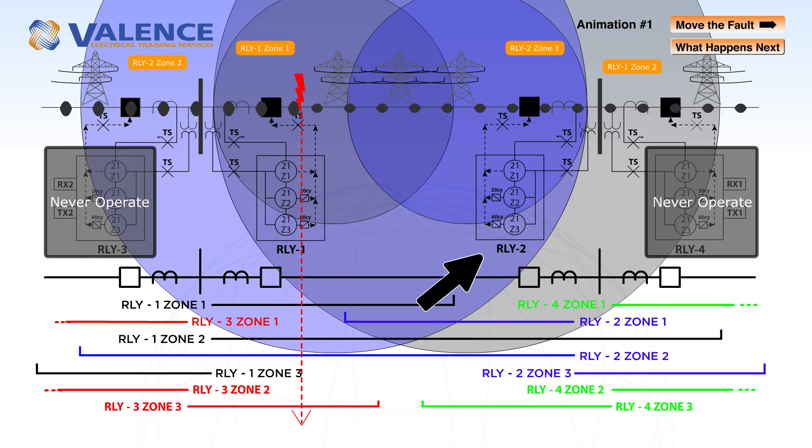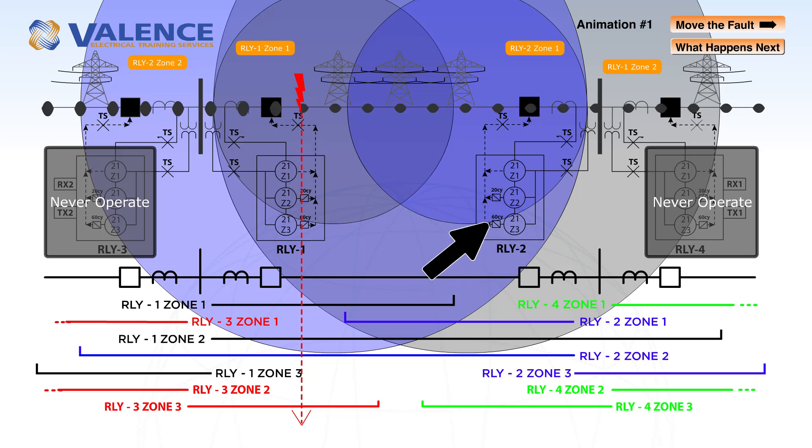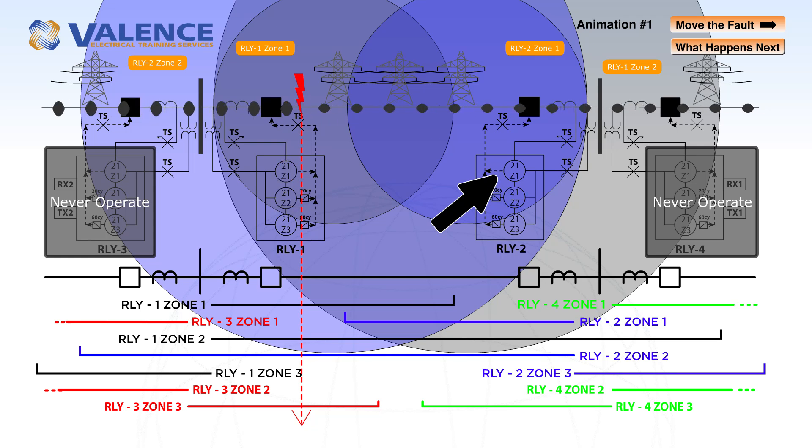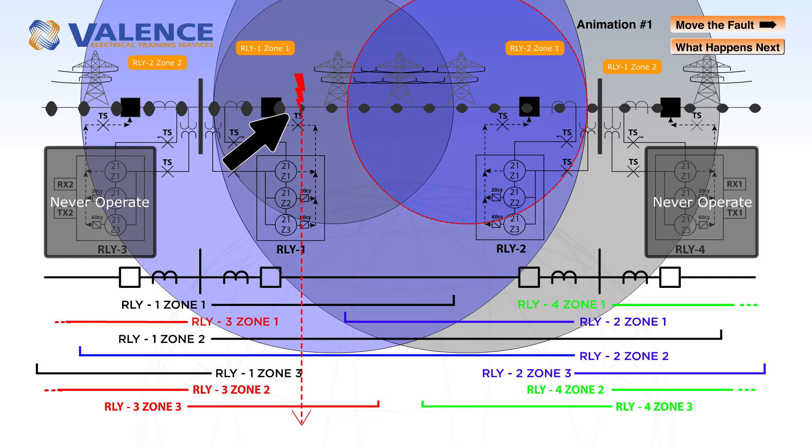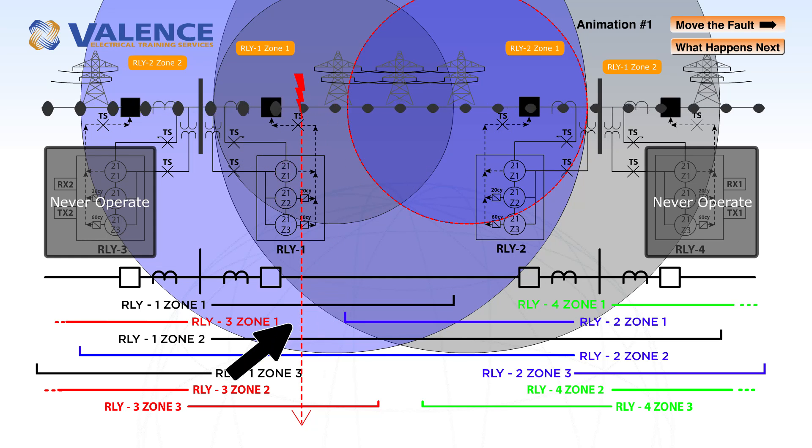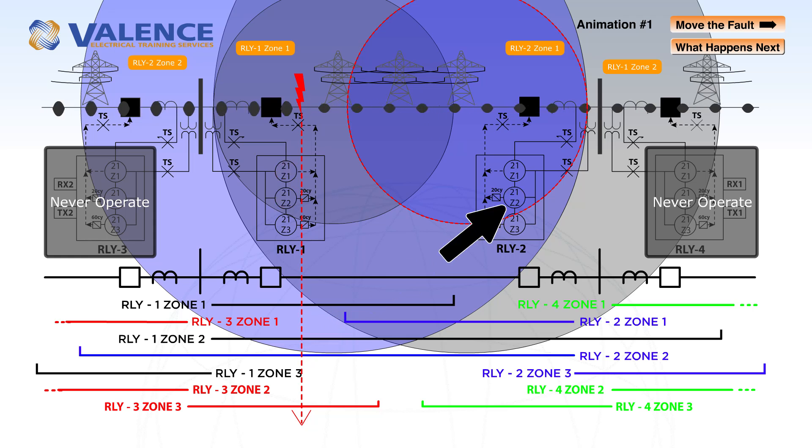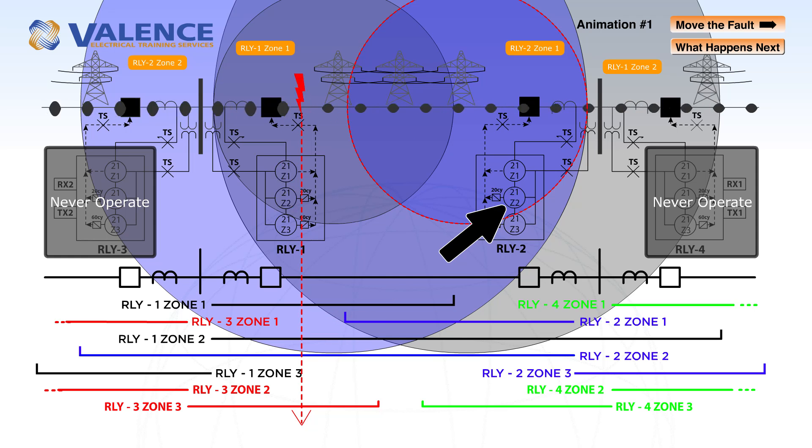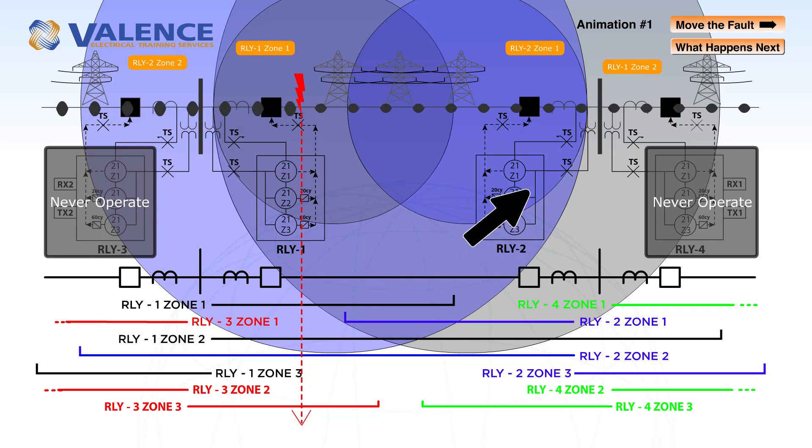If we look at relay 2, it's not going to see zone 1 because the fault is beyond the zone 1 settings. Relay 2 will see a zone 2 pick up as soon as the fault starts.